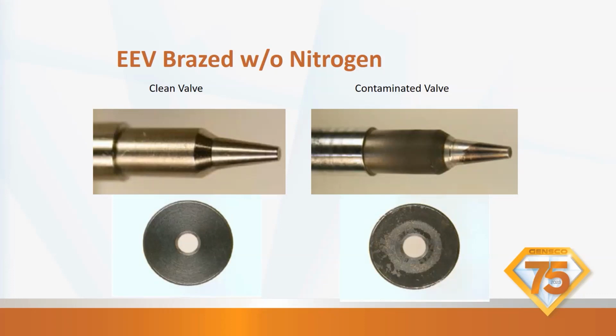So you go out to troubleshoot it, and it works today because it's 75 degrees outside and the valve's kind of in the middle. So it's going to open up a little bit and close back down. It's not going to try to open all the way because it doesn't have a big heat load. As soon as it gets hot outside, it tries to open up all the way. Now the AC doesn't work right because of the contaminated valve. Okay. So this makes our jobs a lot harder.